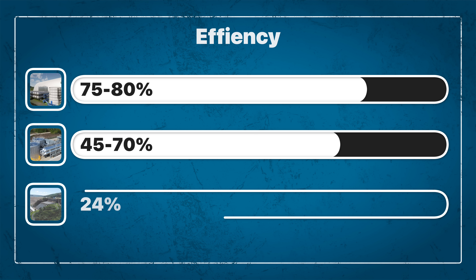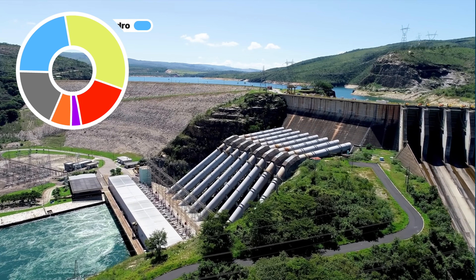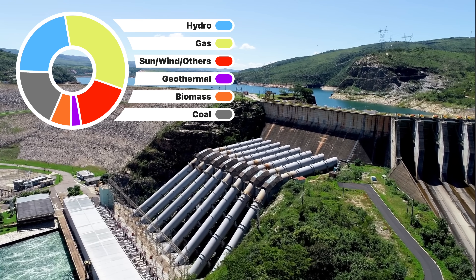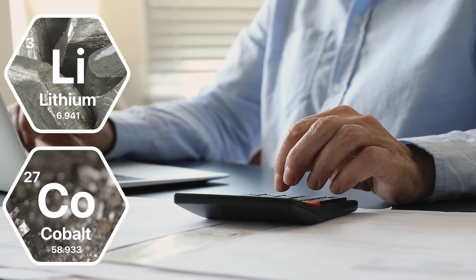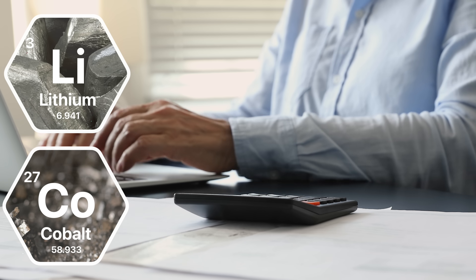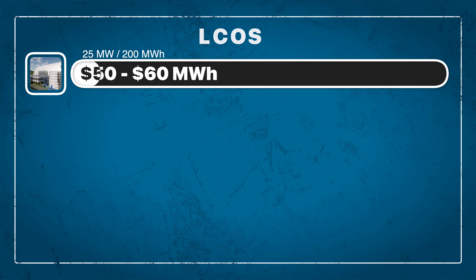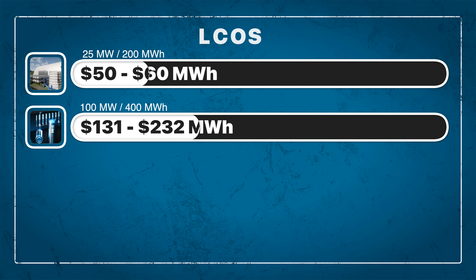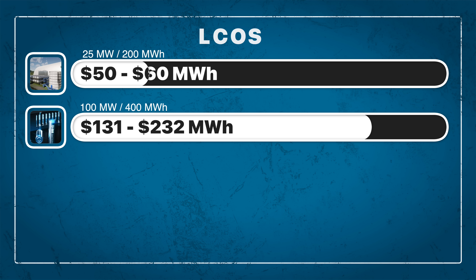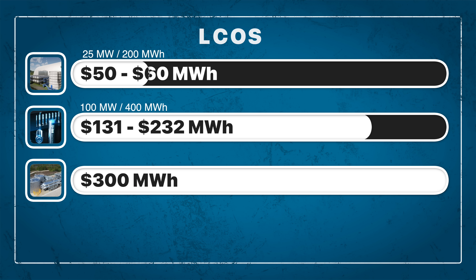These efficiency ratings compare pretty closely to pumped hydro storage systems, which can achieve around 80% efficiency. Pumped hydro currently makes up around the same percentage of Italy's grid as wind, solar, and other renewables combined. But where the CO2 battery truly shines is in cost. Since this battery uses no special equipment and no exotic materials like lithium or cobalt, the cost can be brought far below the competition, including lithium-ion batteries. According to Energy Dome CEO Claudio Spadacini, the levelized cost of storage, or LCOS, for a full-scale 25-megawatt, 200-megawatt-hour plant will be in the range of around $50 to $60 per megawatt-hour of stored energy. For comparison, the LCOS for a 4-hour, 100-megawatt, 400-megawatt-hour lithium-ion battery system is between $131 and $232 per megawatt-hour, while compressed air storage systems can cost a whopping $300 per megawatt-hour or more.